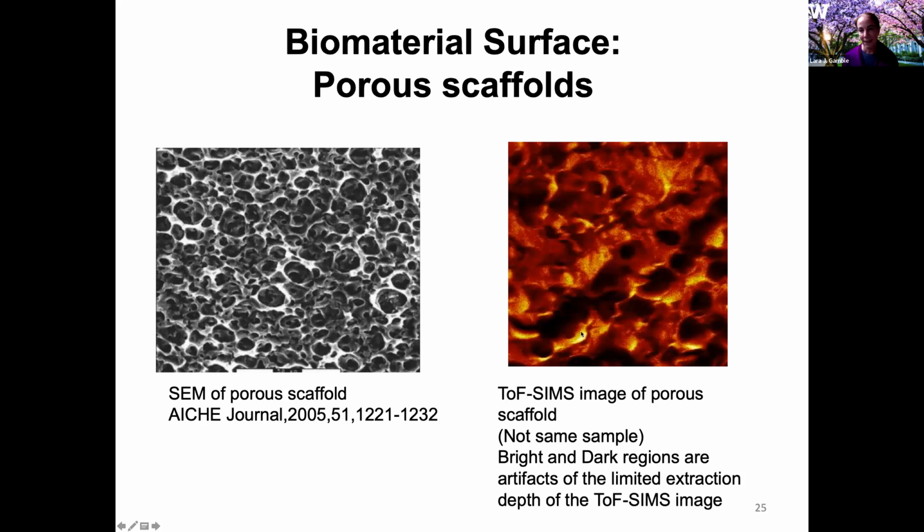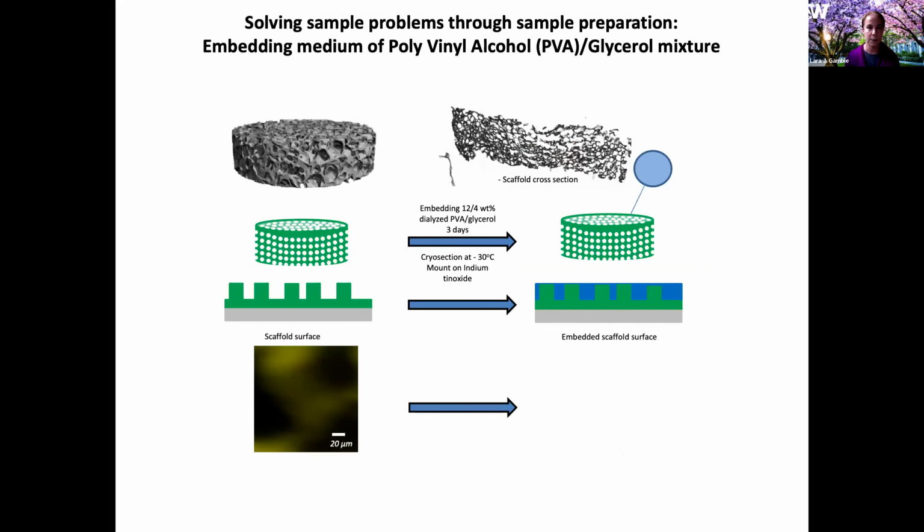It looks somewhat like a porous scaffold, but TOF-SIMS is generally optimized to work on a flat surface. And when we're getting those ions from different levels within the sample, different heights, it makes the signal very hard to understand. Plus it actually makes the spectra very broad, and I didn't include that here. And so with your peaks being broad, it's very hard to identify the exact position of those peaks and therefore the exact molecule that it's representing.